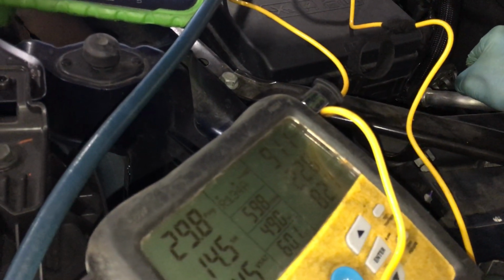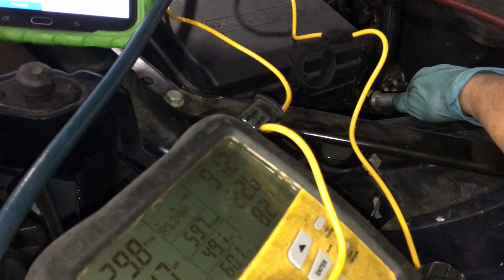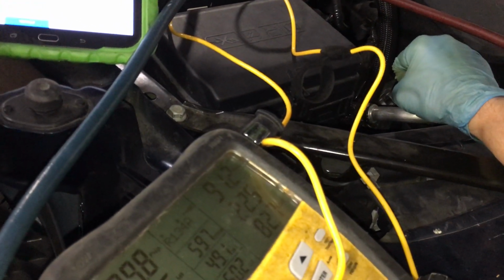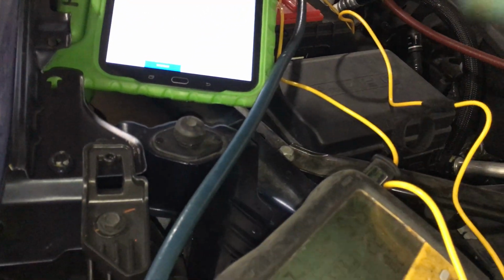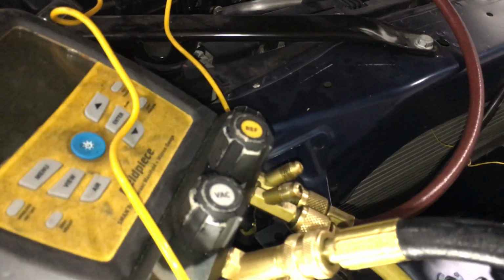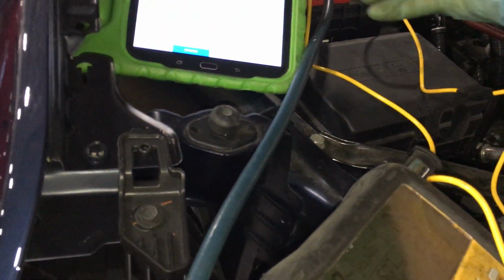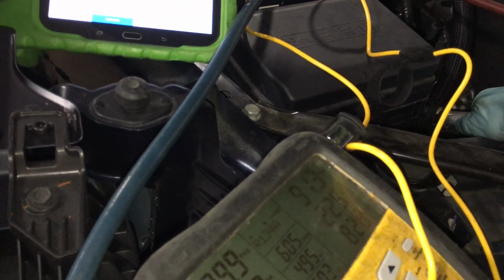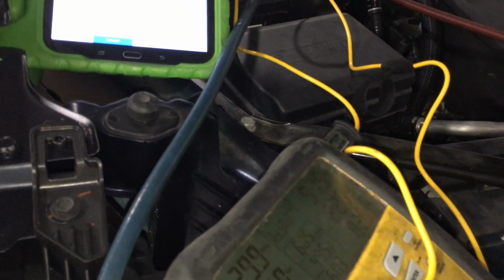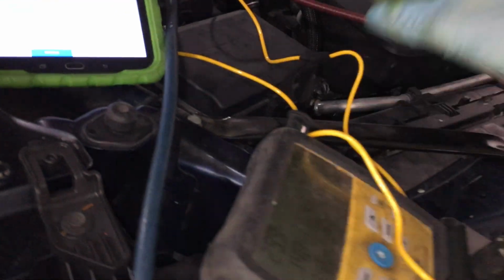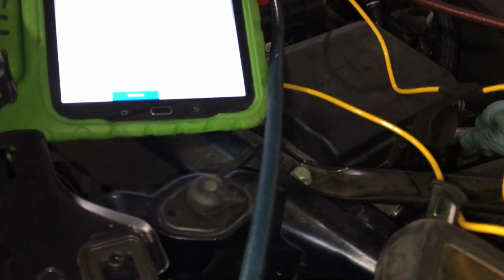And this has become more drastic on hotter days. So definitely for those guys who use the little cans and they grab a line and they try to determine, they'll have a warmer suction line temperature, and they'll be grabbing that suction line and they'll be overcharging the system because the hot liquid gas is exchanging its heat with the suction line, and they're grabbing this line right here, and they're getting a warmer temperature, thinking the old school method that they need to add more refrigerant. This is for the technicians who use the beer can cold method. That don't work no more.